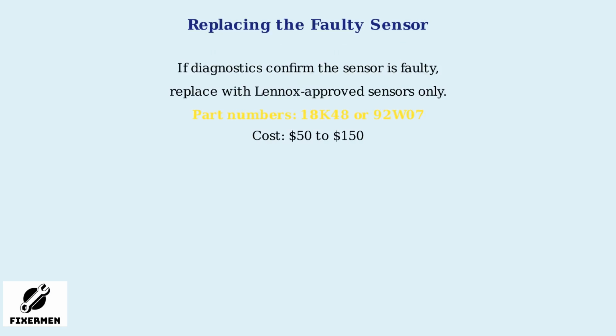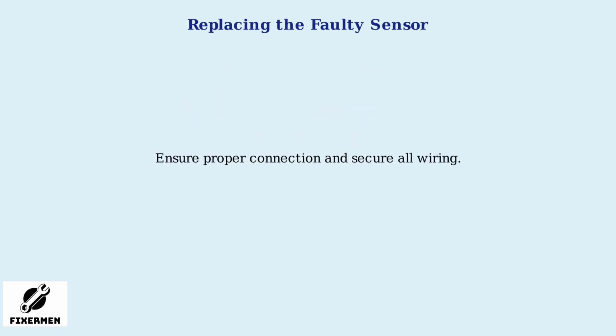If your diagnostic check confirms that the sensor is faulty, you'll need to replace it. Use only Lennox-approved replacement sensors with part numbers such as 18K48 or 92W07. These sensors typically cost between $50 and $150. Ensure the new sensor is properly connected and that all wiring is secure.